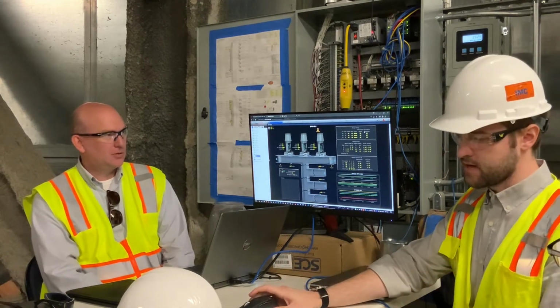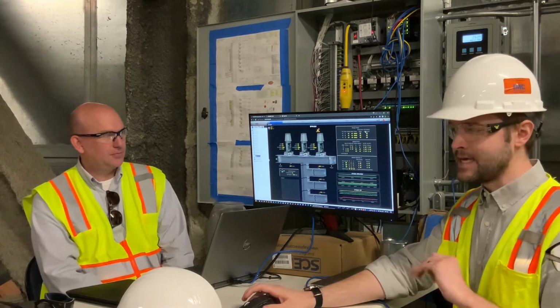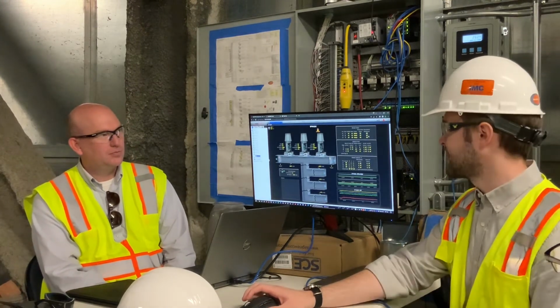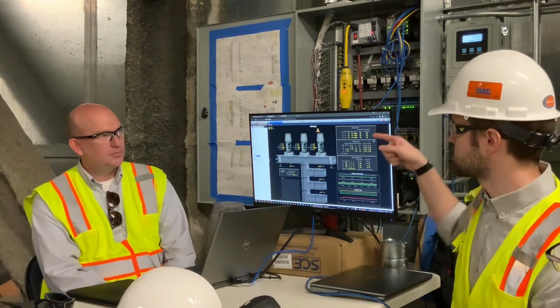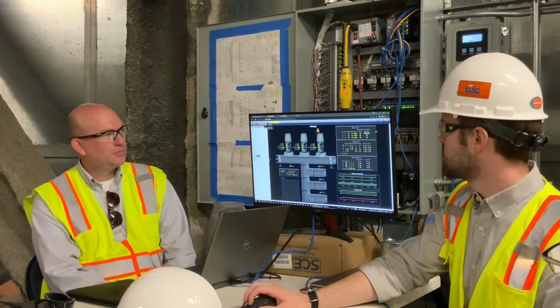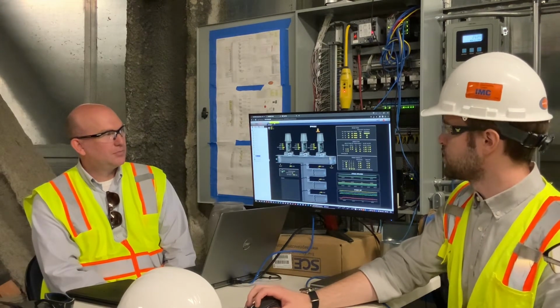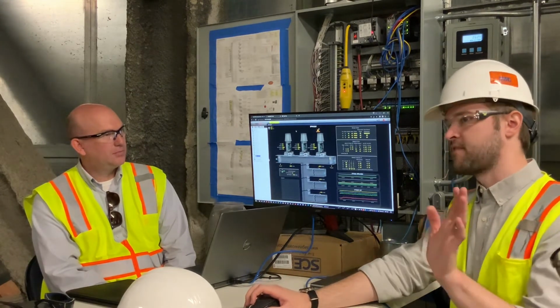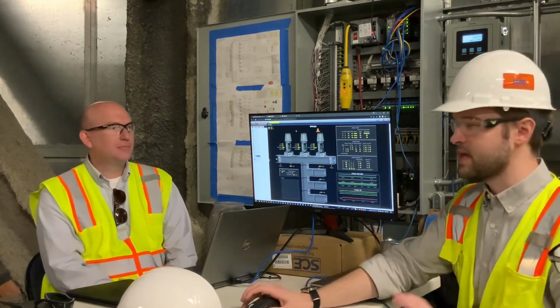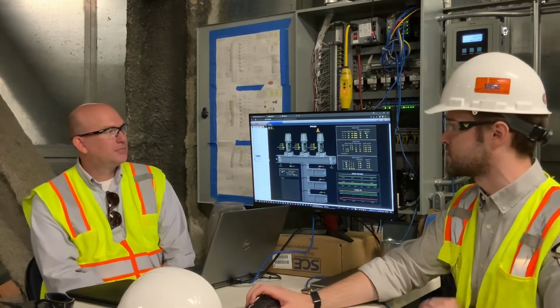On the other side of that, if you do want to turn one fan off and want the system to keep running, the easiest way to do that by far is to click maintenance mode here, and then click accept. It'll take that fan out of the sequence and just run whatever else is available to run. That's by far the easiest way to do this. There are other ways to do it that I don't really recommend.